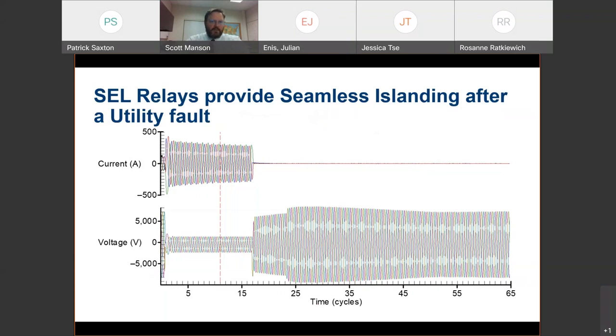Here's an example where there was a fault. You can see the current went up, and this is the phase A, B, and C symmetrical fault current of a three-phase to ground fault. Again, this comes from a protective relay. The voltage went low. I can tell immediately, like a doctor could see from a cardiogram, I can tell you there's synchronous generators on this system. I can also tell you there's impedance to the fault at some distance away. There's a lot to decode from this, but that's not where we're going. This particular relay happened to be at the point of common coupling to a utility between a microgrid and a utility. This is a 751 relay and programmed to what's called decouple. Via the 1547 ride through requirements and provide protection and provide control and provide load shedding and a whole lot more, all in one box.